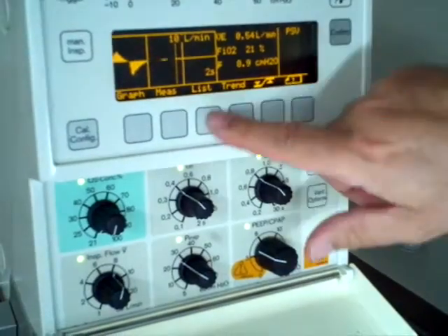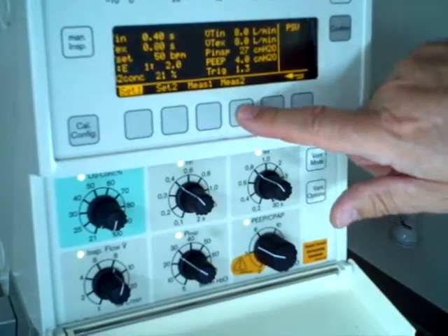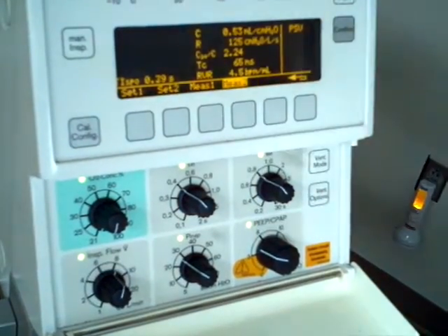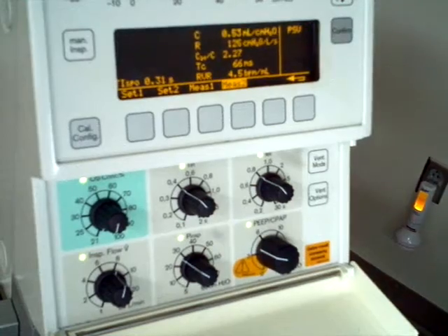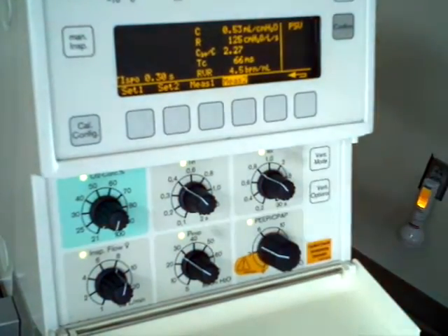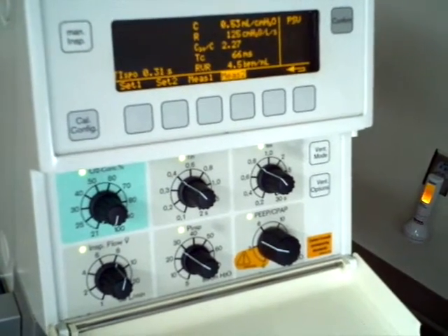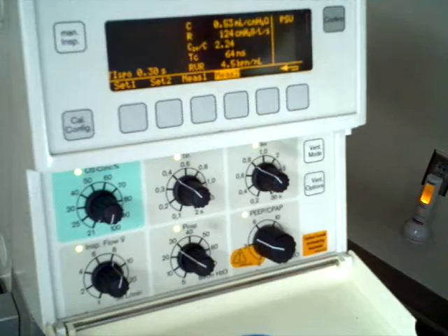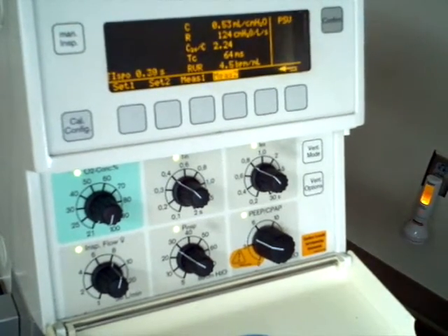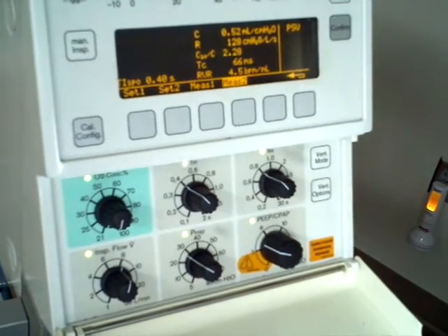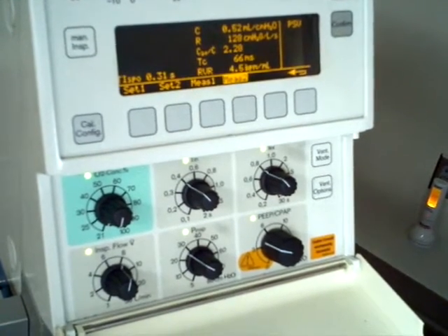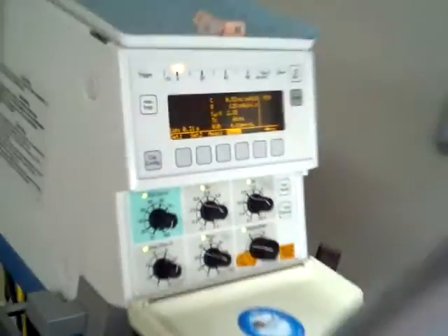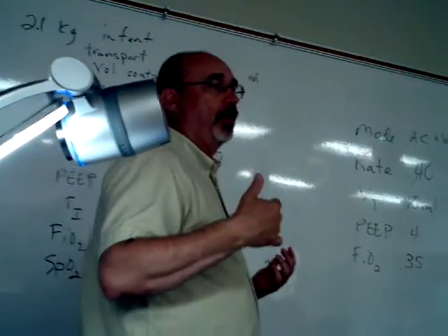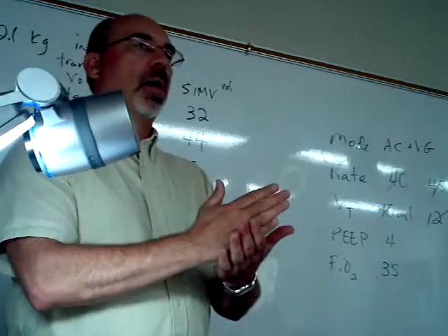Now, there's something in pressure support. If you go to your list and your measure 2 screen, that shows us our actual inspiratory time. In other words, the actual time the baby's taking is 0.3. What's my setting? 0.4. So in this mode, the inspiratory time is an actual limit on the time. So the baby can't take longer if they want to, but it'll limit it to 0.4 seconds before the vent kicks in. In other words, if you have that set too tight and the baby feels like taking a 0.45 inspiratory time, it'll cut them off. So you want to make sure you don't have that set too tight.